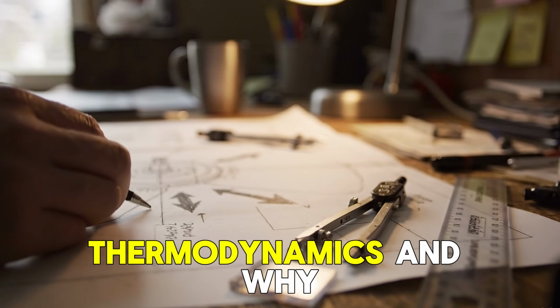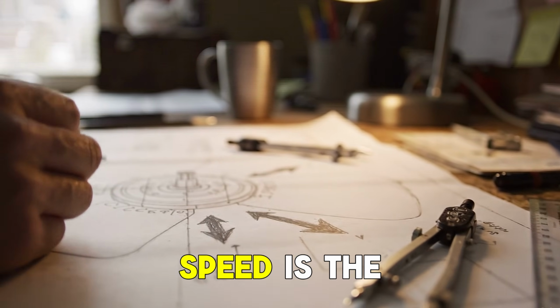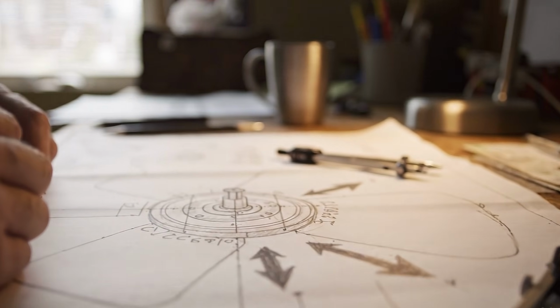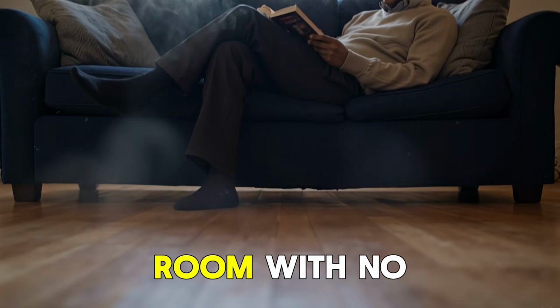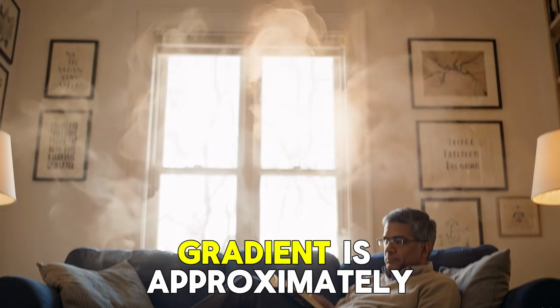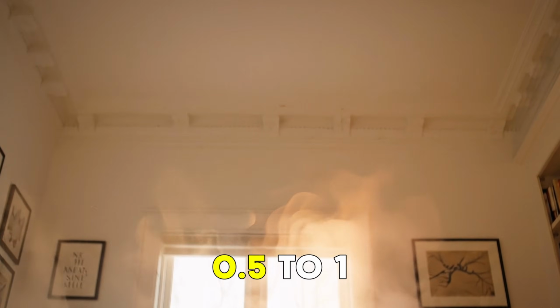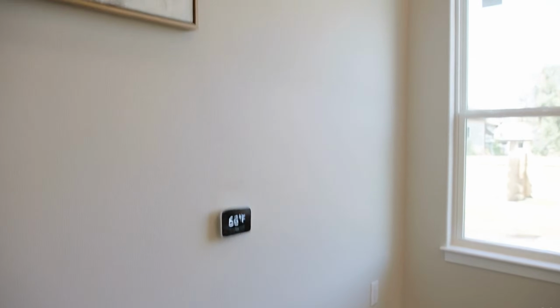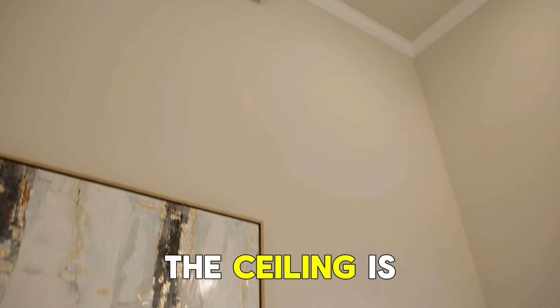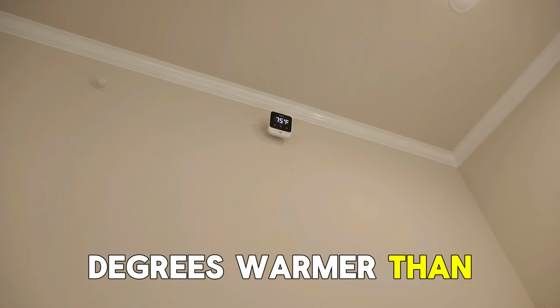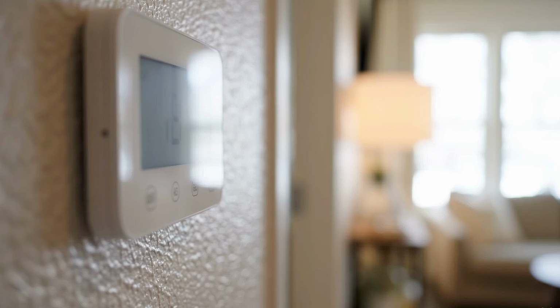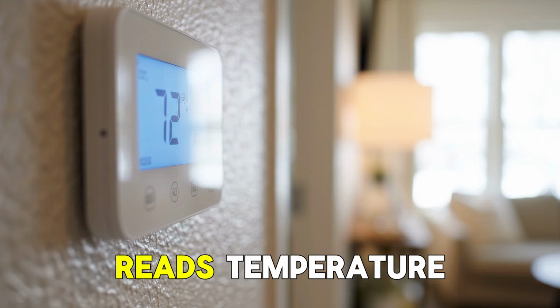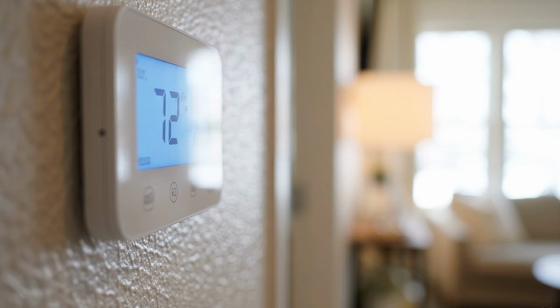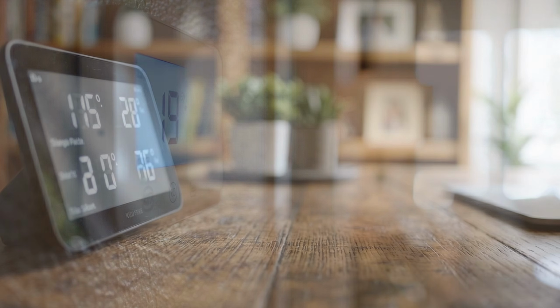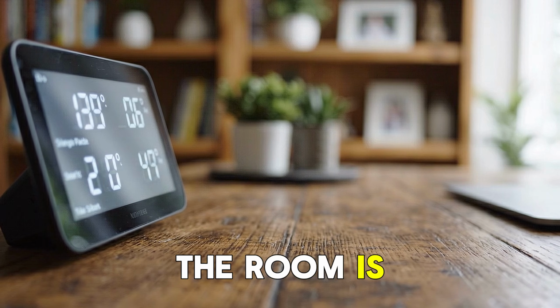Here is the thermodynamics, and why clockwise at low speed is the specification. In a heated room with no air movement, the temperature gradient is approximately 0.5 to 1 degree per foot. In a 10-foot ceiling room, the ceiling is 5 to 10 degrees warmer than the floor. The HVAC thermostat reads temperature at installation height. The average air temperature in the room is 2 to 5 degrees higher than the thermostat reading.